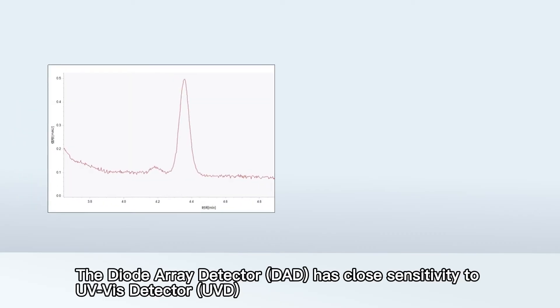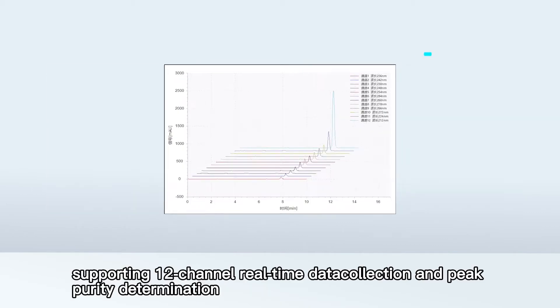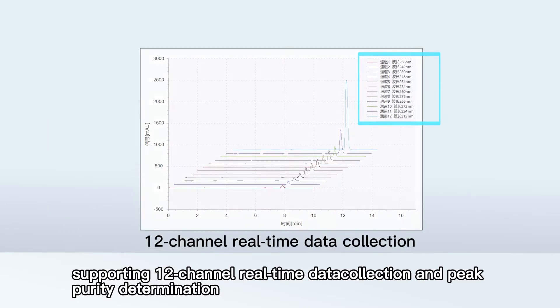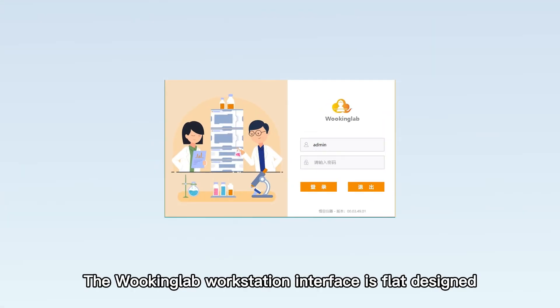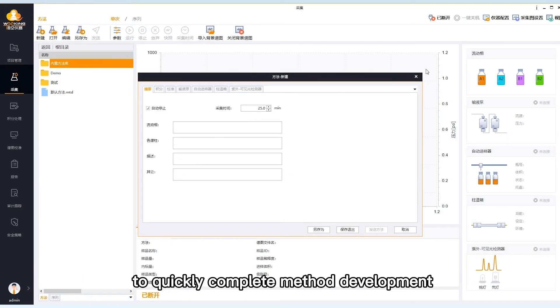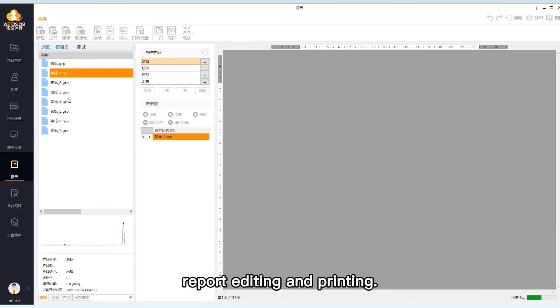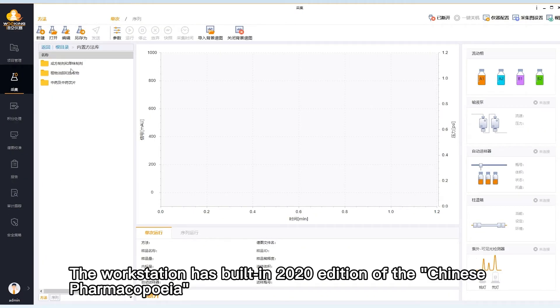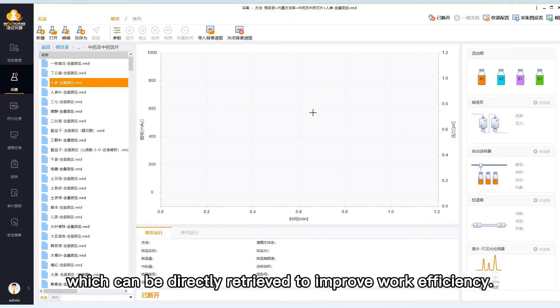The DAD has close sensitivity to the UVD, supporting 12-channel real-time data collection and peak purity determination, which makes the results accurate and precise. The Wookinglab workstation interface is flat designed to quickly complete method development, data acquisition, data processing, report editing and printing. The workstation has a built-in 2020 edition of the Chinese Pharmacopoeia and Chinese Veterinary Pharmacopoeia Standard Method Database, which can be directly retrieved to improve work efficiency.